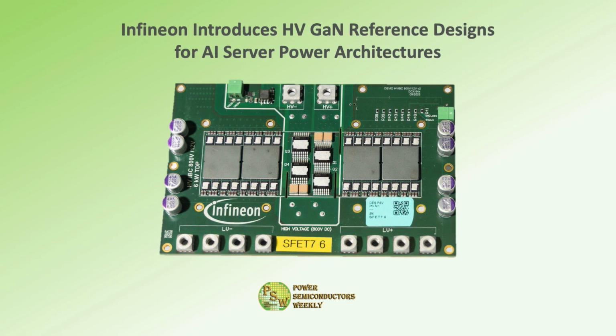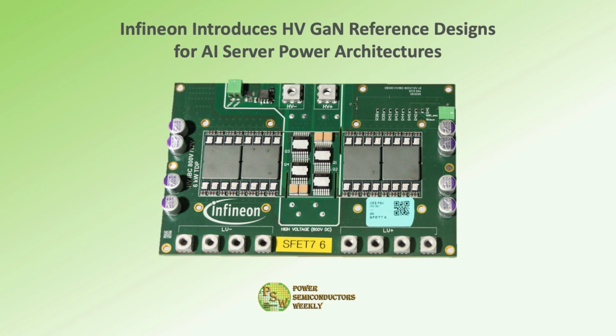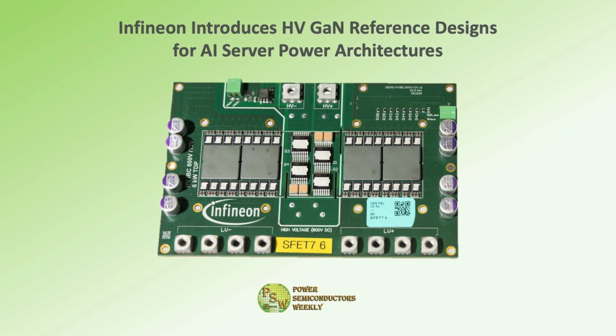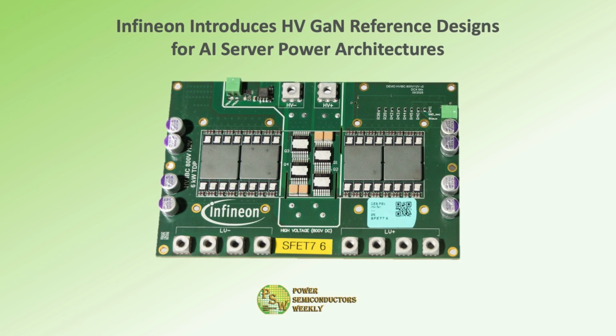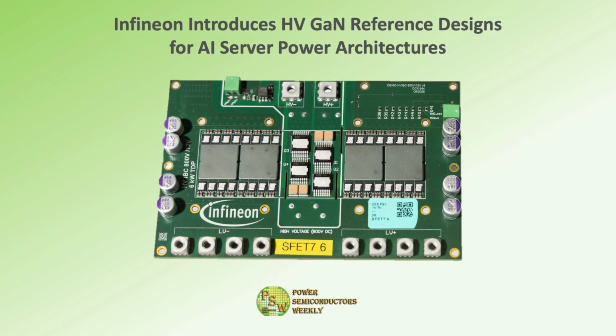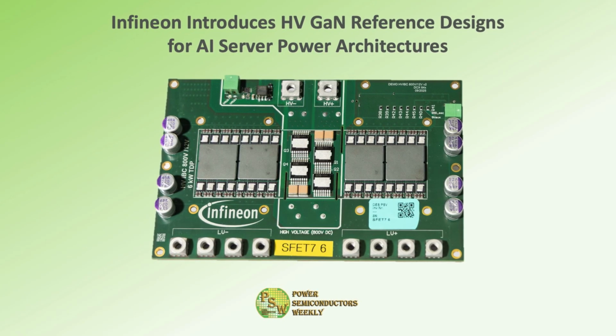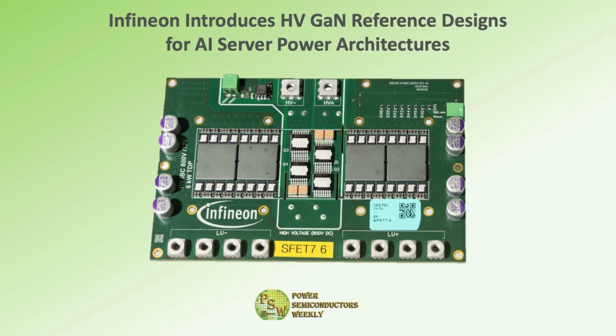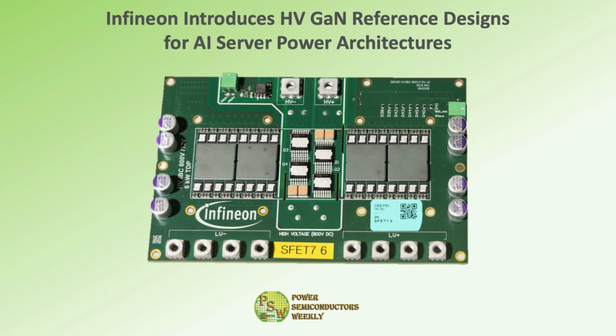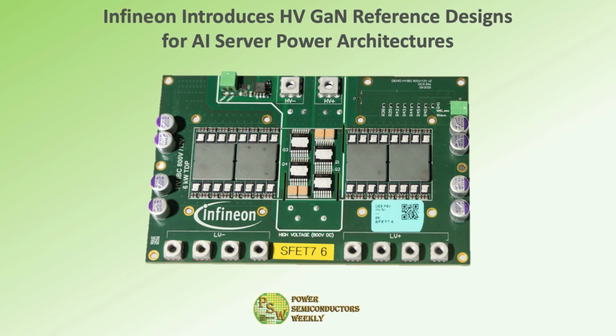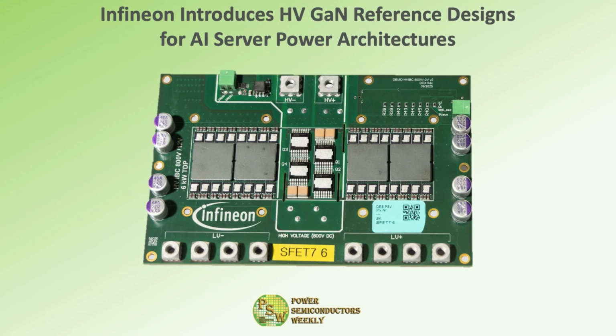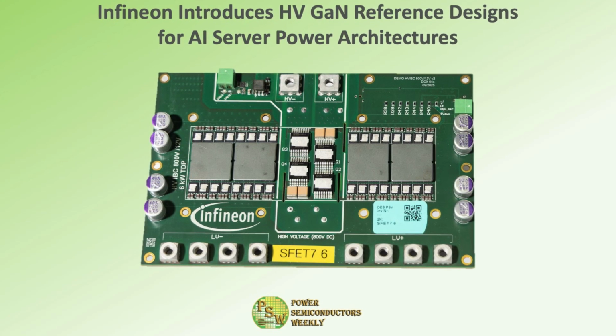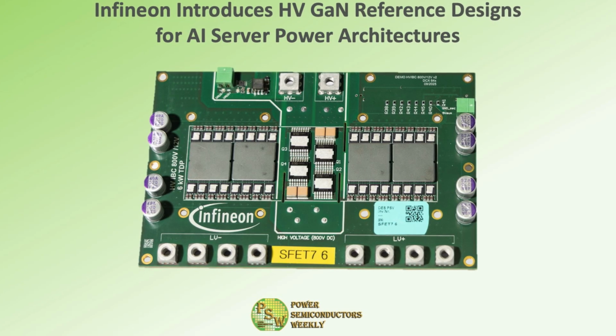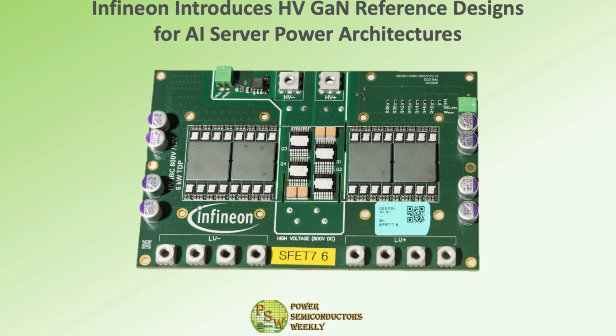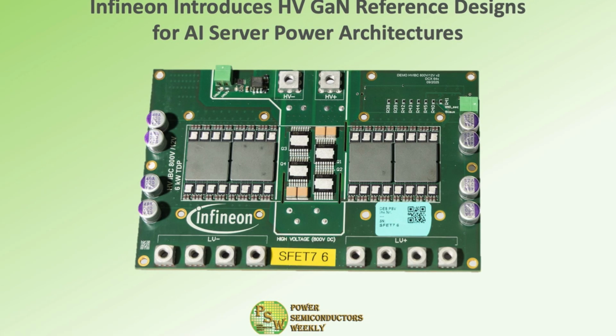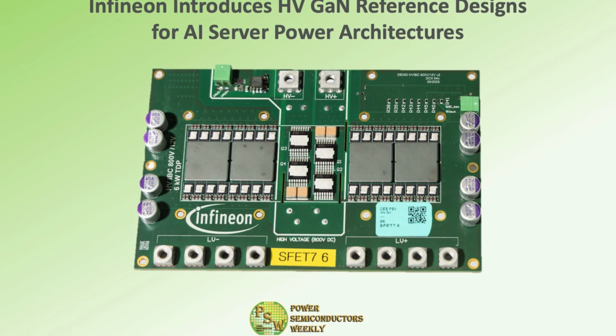Infineon Technologies released two high-voltage intermediate bus converter reference designs to speed adoption of plus/minus 400-volt and 800-volt DC AI server power. Using 650-volt CoolGaN, one design converts 800-volt (plus/minus 400-volt) to 50-volt, delivering over 98% efficiency and scaling to 6 kW in a compact architecture. The second converts 800-volt directly to 12-volt via half-bridge LLC and matrix transformer, reaching up to 98.2% peak efficiency and over 2.3 kW per cubic inch power density for ultra-thin server boards.